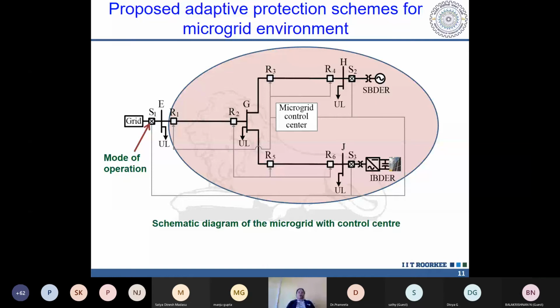So we have proposed one microgrid control center. There are many ways to present this. Now researchers are avoiding the traditional relay concept - they are trying to put intelligent electronic devices, IEDs, at the two terminals of the lines, sensing data and sending it to a central control operator. The central control operator takes all the decisions - which line has the fault, which circuit breaker should open, which renewable source should be reconnected, and so on.